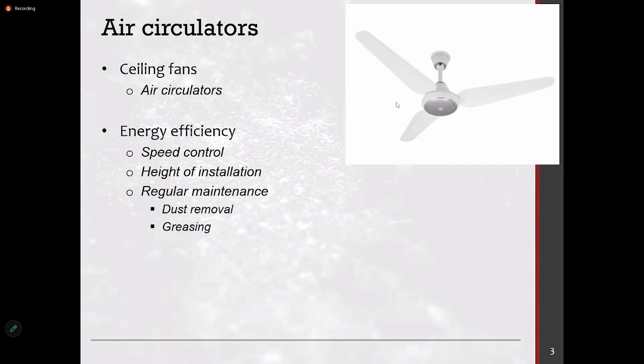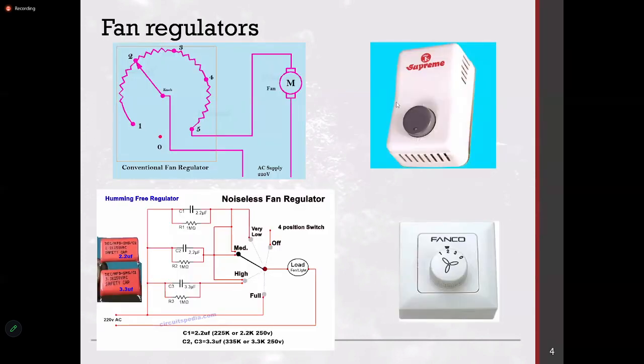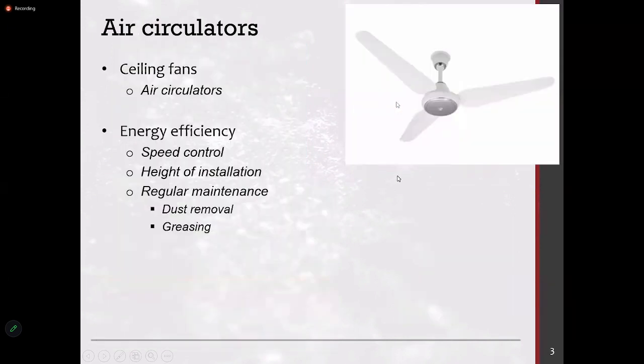So looking at energy efficiency, the key is to ensure speed control of these fans, because in the good old days we had these transformer type regulators, which are transformer controlled and modulated, but whatever the speed you put, the consumption is the same. But now you have very high-end, electronic type regulators. You can see the weight is also very less in the present regulators. So they have a kind of capacitor control. So the lower the speed, definitely the lower the power consumption. So speed control is one key. So you ensure that you run it only as per the requirement.